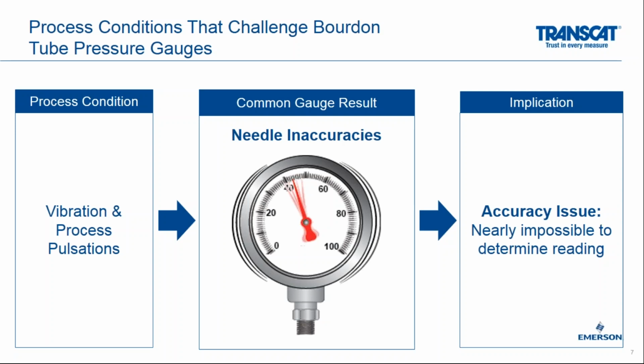I'm sure everyone, whether you use gauges frequently or not, has seen a gauge where the needle is moving around back and forth. And the challenge here is that from an accuracy standpoint, you can't really determine the reading. The whole goal of this pressure gauge is to give you some insight into what's going on in the process. But if you can't tell what the gauge is reading in the first place, there's very little insight that you can take when there's vibration or pulsation.